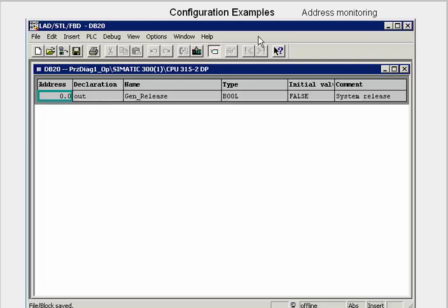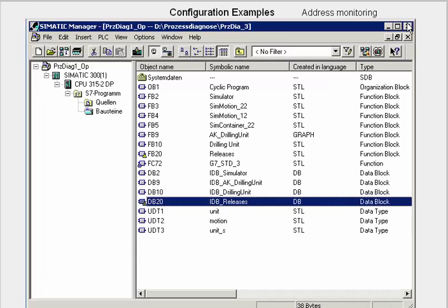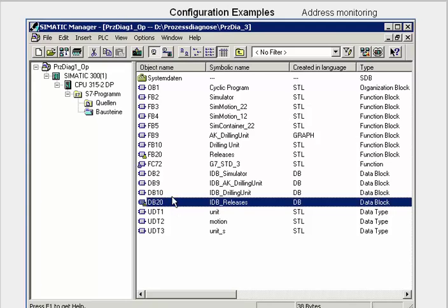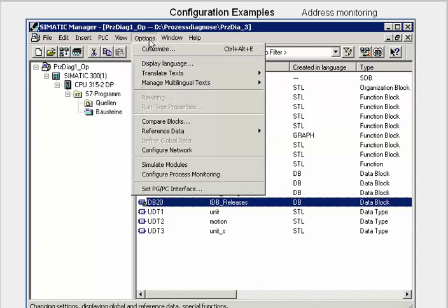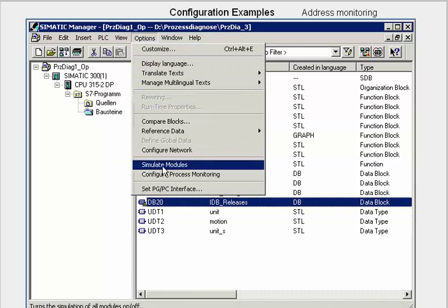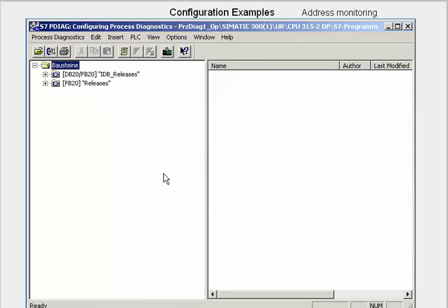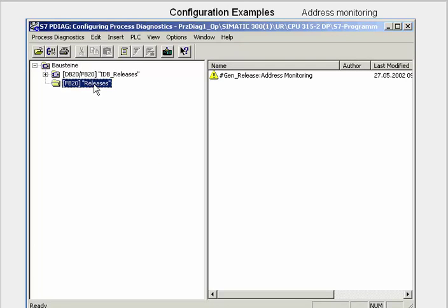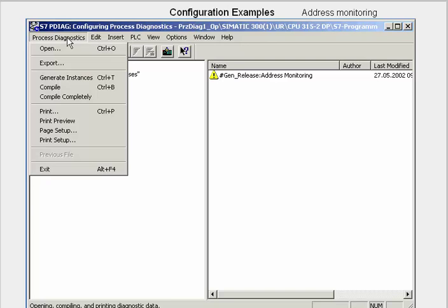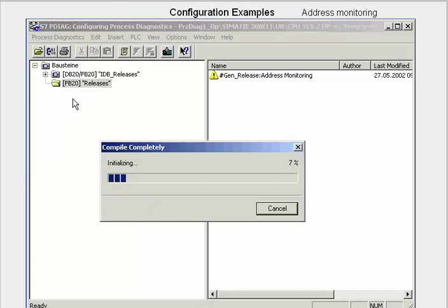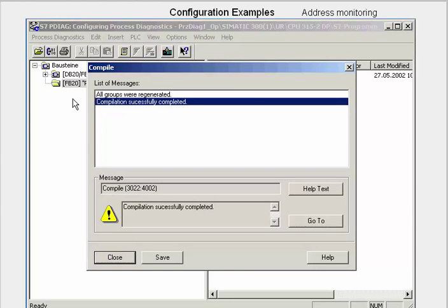In the block overview, we see that after saving the block, DB20 has also been marked as supporting diagnostics. We now call the process diagnostics application S7 PDIAG. In the explorer view in the left window, we see all the units of the program that support diagnostics. In the right window, you have a display of all the signals monitored and also the type of monitoring. Via the menu item Process Diagnostics — Compile Completely — we now generate all the monitoring blocks.